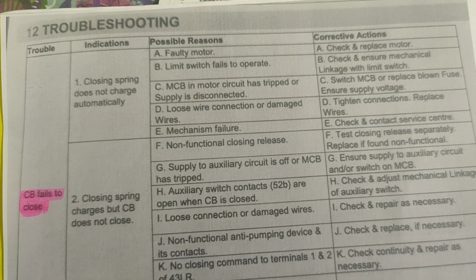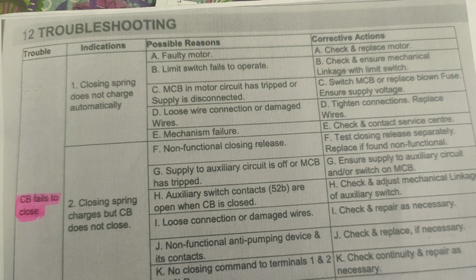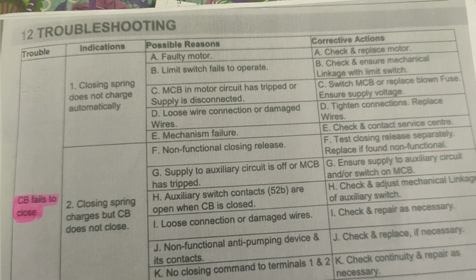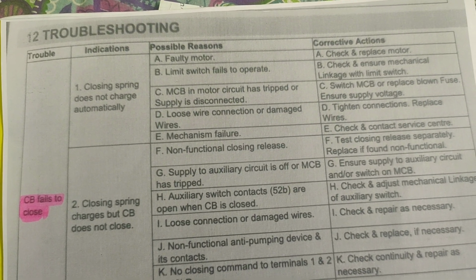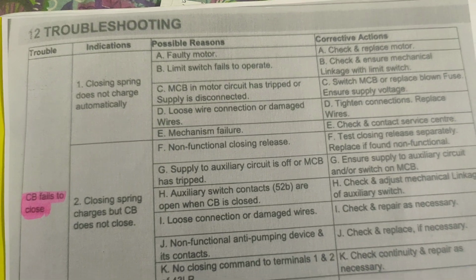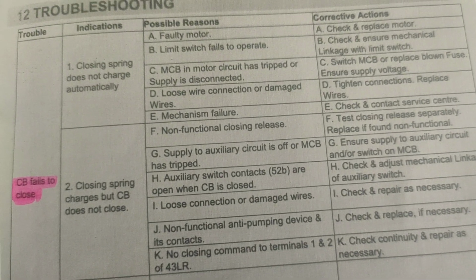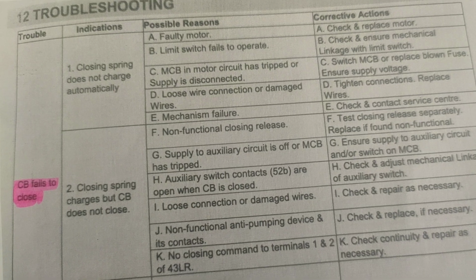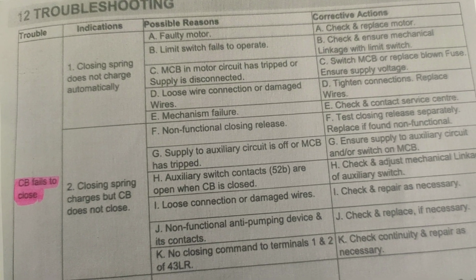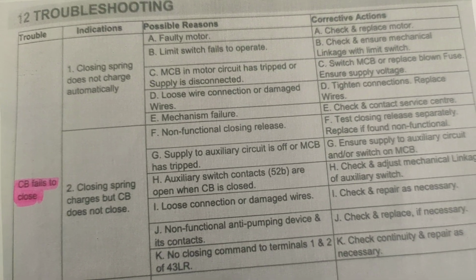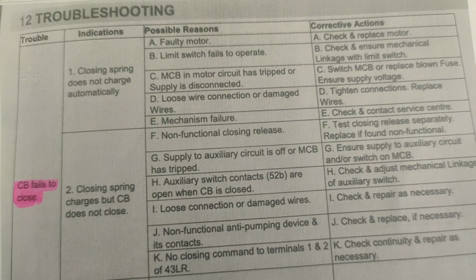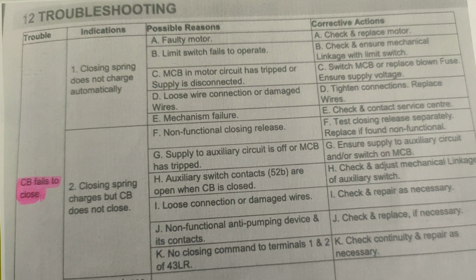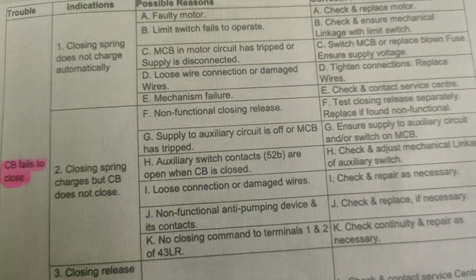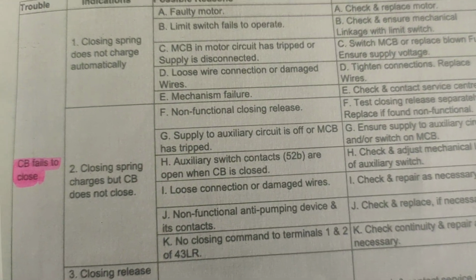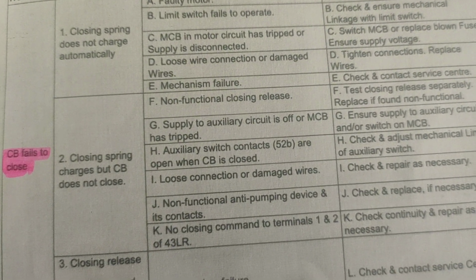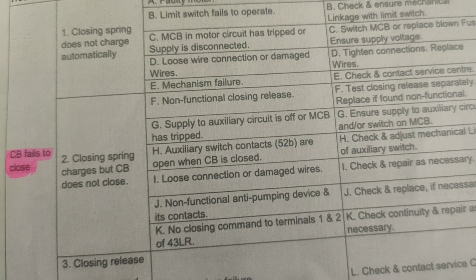The circuit breaker failed to close, the circuit breaker failed to open, the spring charging problem, circuit breaker coil problems, circuit breaker dashpot problems, and circuit breaker mechanical on-off operation not in easy condition. In such cases you have to overhaul the breaker in consultation with the manufacturer or the OEM. But the first problem is that the circuit breaker fails to close. It is the main criterion you have to fulfill.